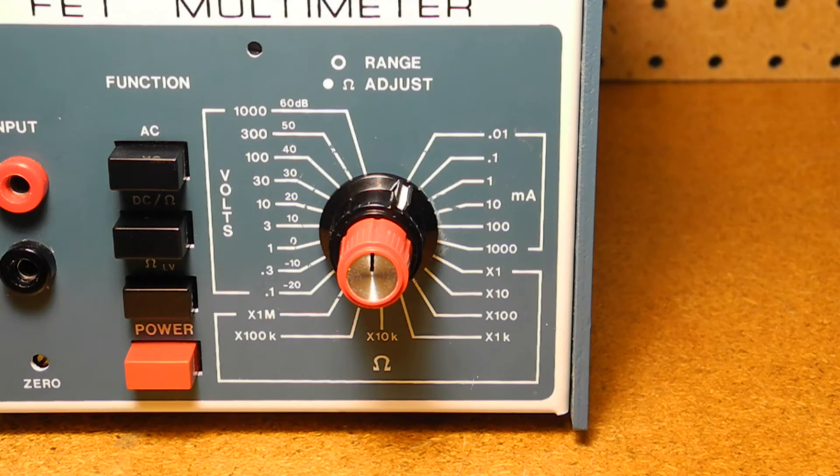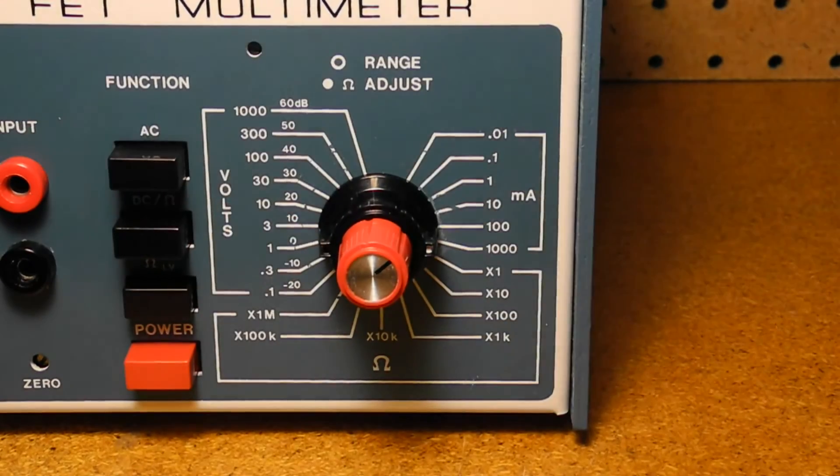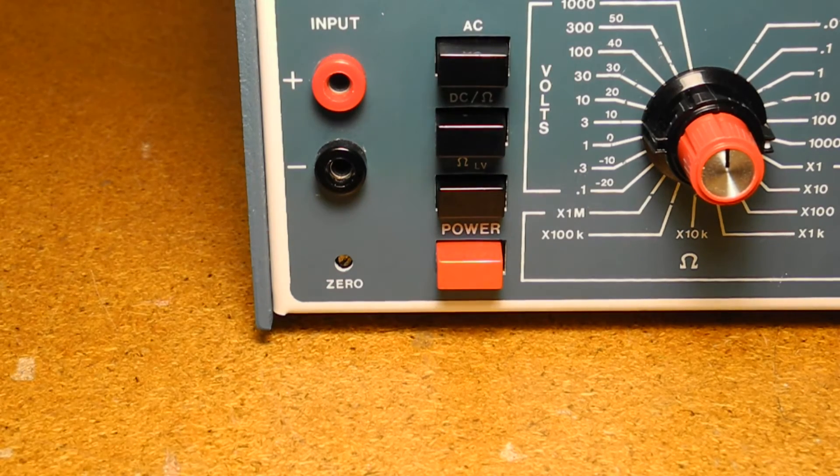The range switch selects the voltage, current, and resistance ranges. It has 24 positions with a couple of unused positions at the top. The red concentric knob is for adjusting for zero on the resistance ranges when the test leads are shorted. At lower left is a trimmer adjustment for setting the zero value. It needs to be adjusted occasionally.